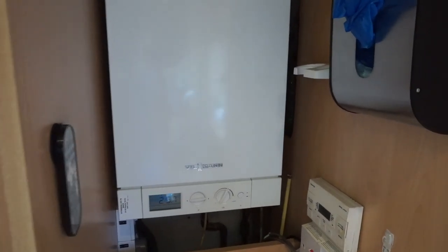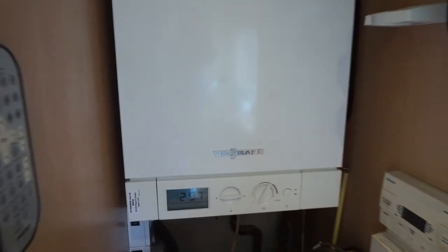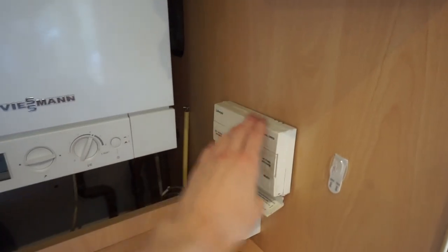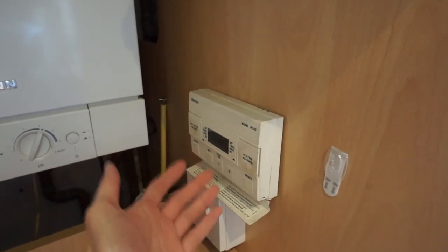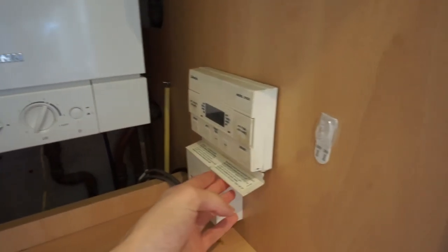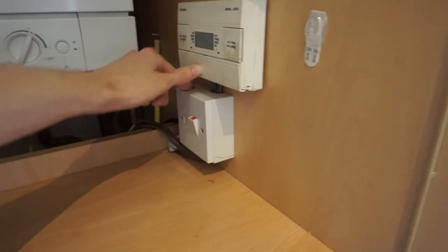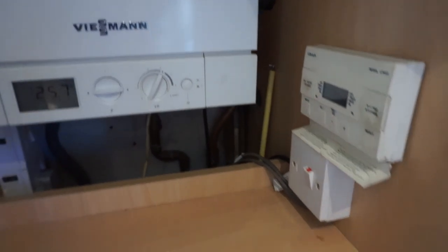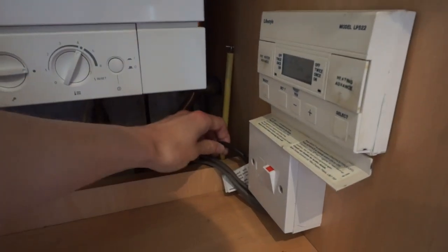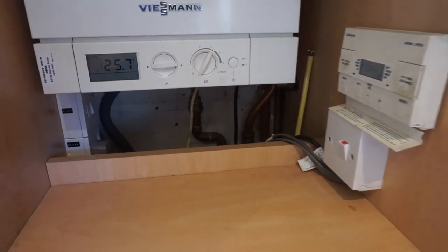Here's the system we're installing into. This is the boiler — a Viessmann Vitodens 100, put in around 2009. It's not a combi boiler; it's a conventional system, so the hot water control is separate. Over here are the existing controls: a standard LP522 programmer, which is fine but it's in a cupboard, a pain to control, and you have to press a million buttons to set the times. We'll be replacing this with the Hive receiver. There are cables here — a black one to the boiler and two twin-and-earth cables going under the floor — so I think there's a wiring centre hidden under the floor with pipes and pumps.